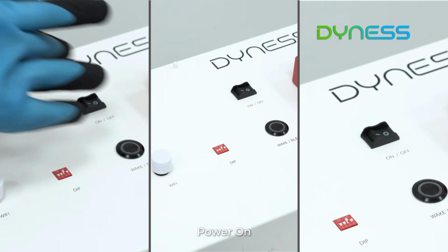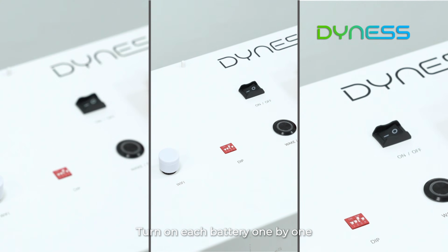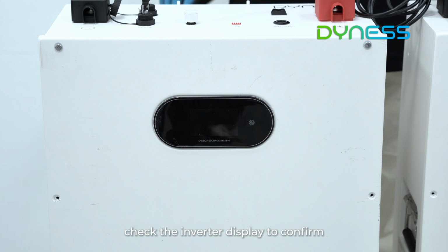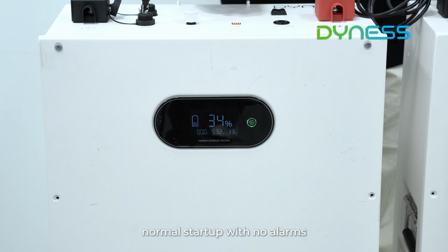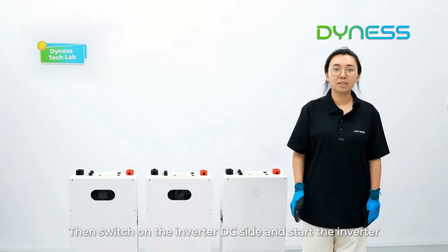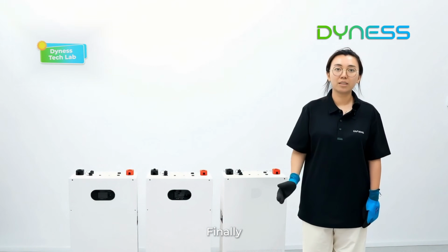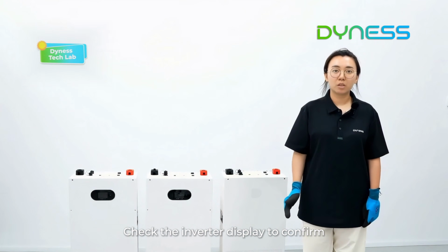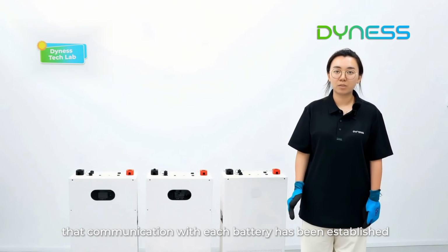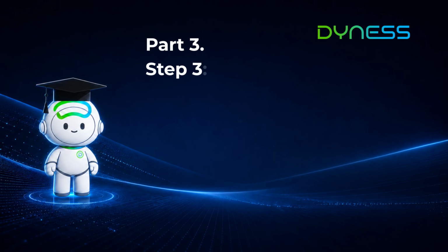Step 3. Power on. Turn on each battery one by one. Check the battery displays to confirm normal startup with no alarms. Then switch on the inverter DC side and start the inverter. Finally, check the inverter display to confirm that communication with each battery has been established.